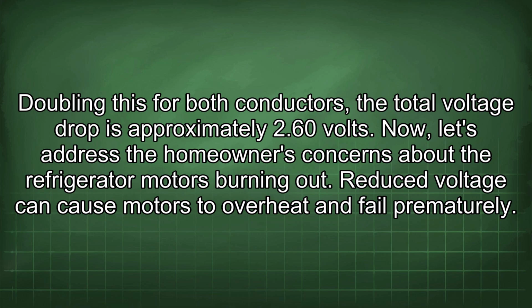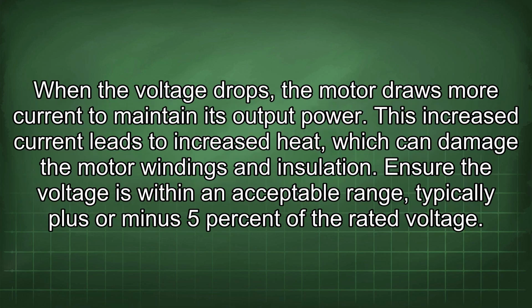Now, let's address the homeowner's concerns about the refrigerator motors burning out. Reduced voltage can cause motors to overheat and fail prematurely. When the voltage drops, the motor draws more current to maintain its output power. This increased current leads to increased heat, which can damage the motor windings and insulation.